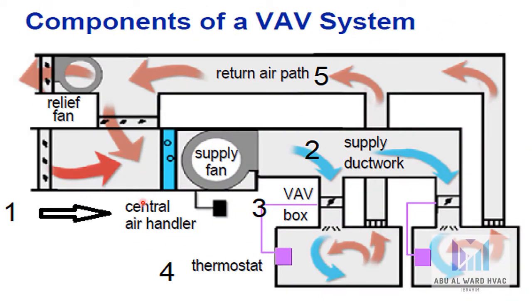A simple VAV system includes the following: we have a central air handler with a variable volume supply fan, a cooling coil, possibly a heating coil, controls, filters, a mixing box, and a return or relief fan. We have VAV terminal units or boxes with a thermostat and supply diffuser for each independently controlled space, a thermostat and unit controller for each terminal unit, and finally a return plenum or duct.